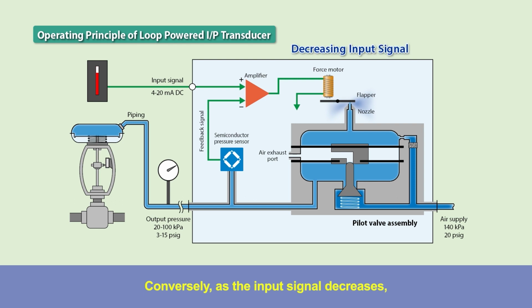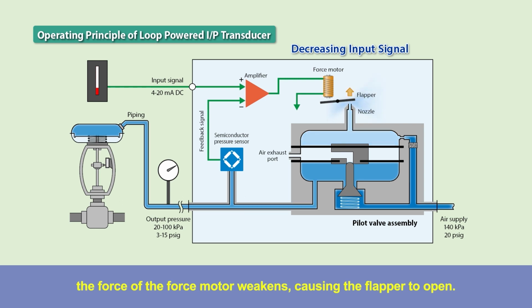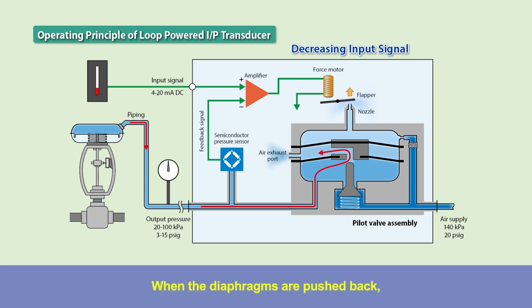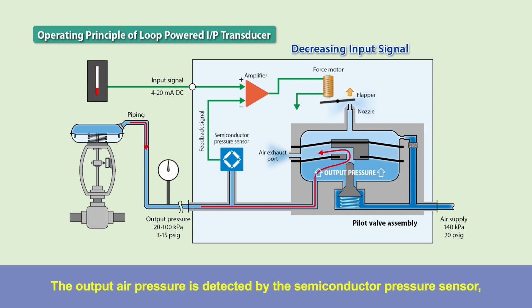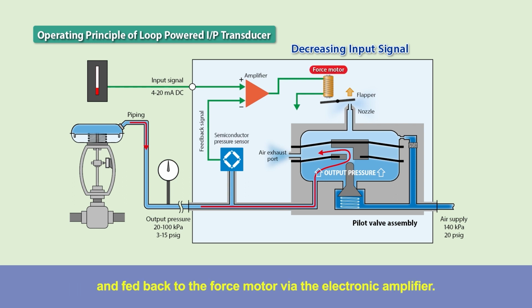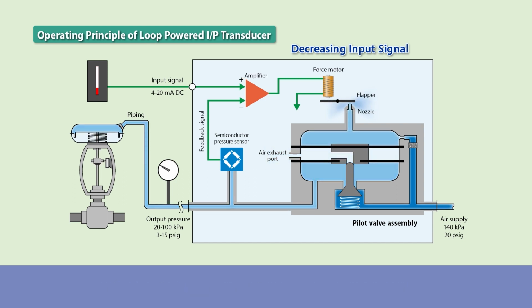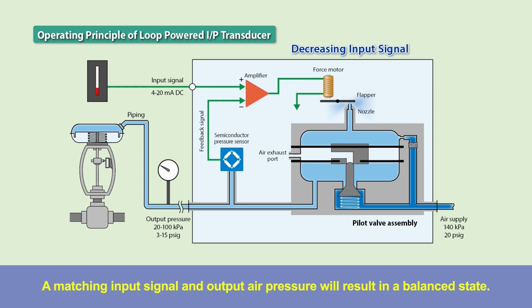Conversely, as the input signal decreases, the force of the force motor weakens, causing the flapper to open. This will decrease the amount of back pressure and allow the diaphragms to push back. When the diaphragms are pushed back, a gap will open between the top of the plug and the discs, from which output air will escape and lower the output air pressure. The output air pressure is detected by the semiconductor pressure sensor and fed back to the force motor via the electronic amplifier. A matching input signal and output air pressure will result in a balanced state.